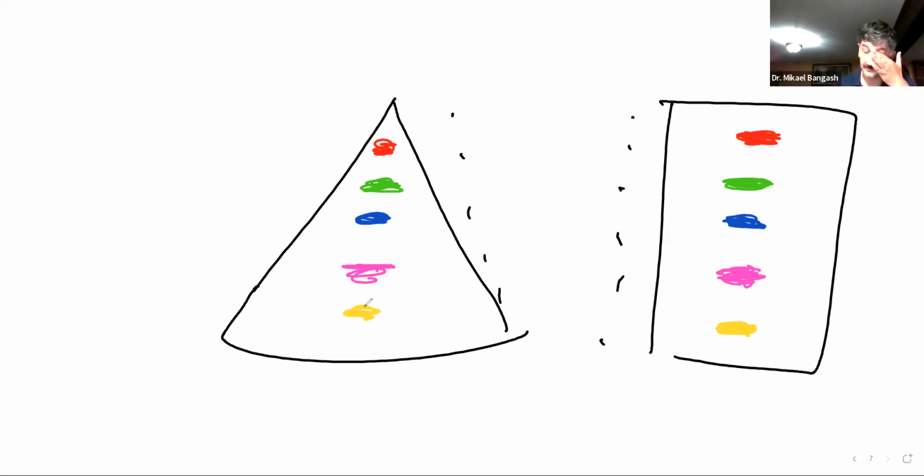That would mainly mean that we had a good axial resolution. How is that good axial resolution produced? Mainly because the pulse was short enough that when the pulse came, it went back, brought this information, and produced it on the image. Then the next pulse goes deeper. Short enough means it can scan this information, bring it up, and show it on the image. And so on.